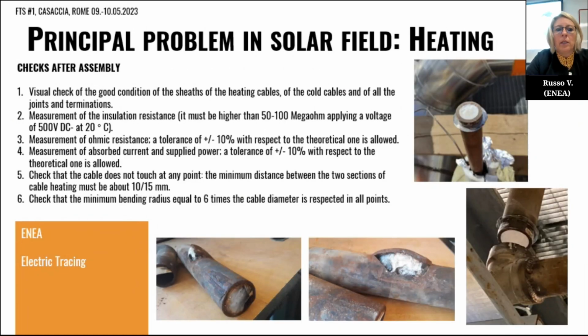As a best practice, after installing the cable, it would be good to carry out some checks, for example a visual check of the good condition of the sheath, or some measurements. For example, we can measure the insulation resistance, the absorbed current, or the power supply. Then we also have to check that the cable doesn't touch itself at any point. In fact, the minimum distance between two sections of the heating cable must be around 10-15 millimeters. And finally, we have to check also the minimum bending radius, which has to be at least 6 times the cable diameter.